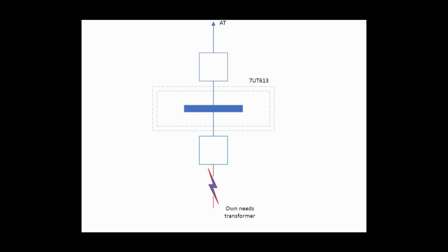In this case, the device protects part of the busbar between the power autotransformer and the auxiliary transformer, which is connected to the delta winding. The short circuit was outside the zone, and the device worked because the current transformer in the second branch was saturated.